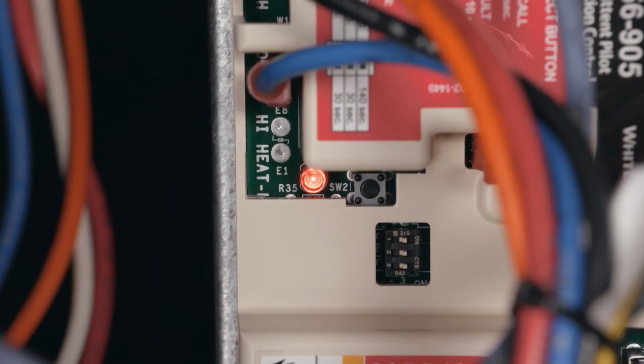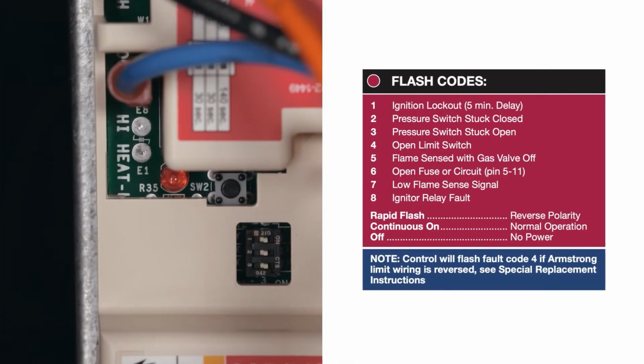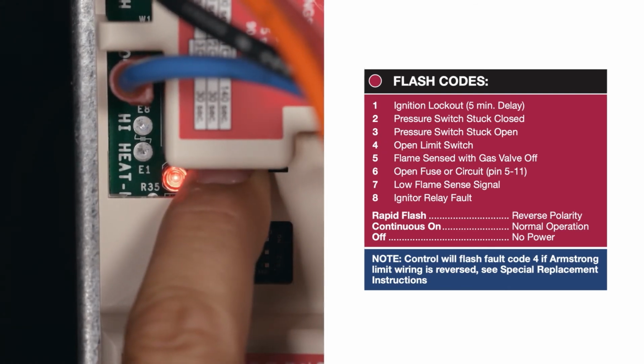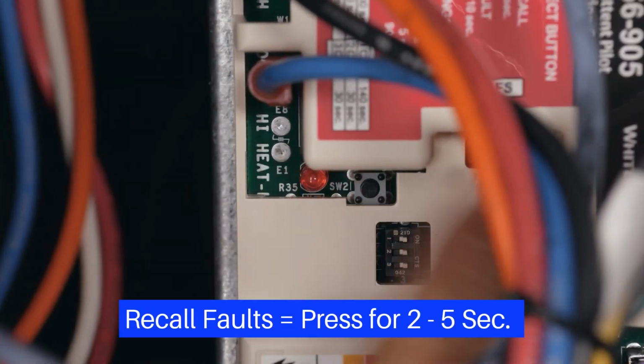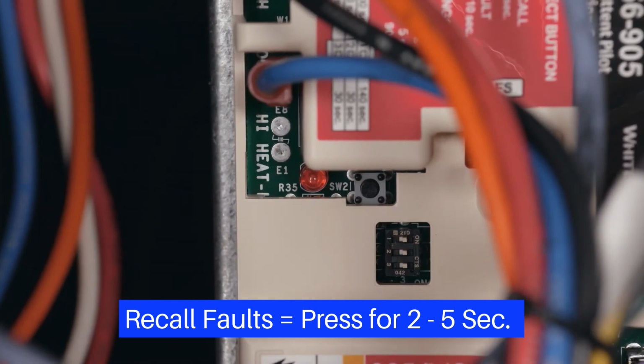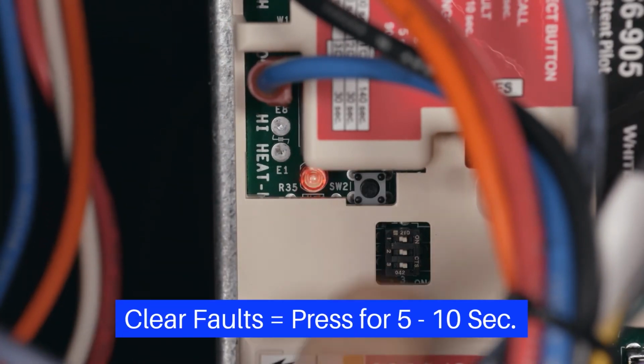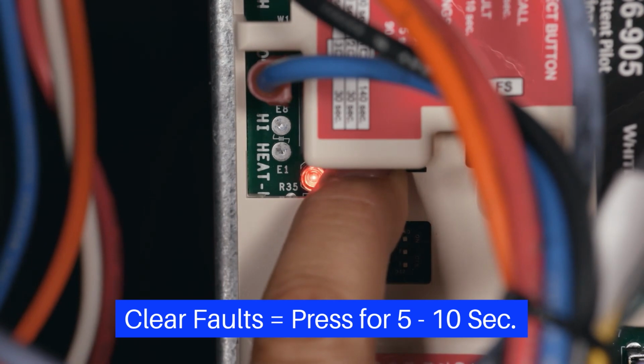The red LED conveys system fault codes. If any faults occur during the cycle, a flash code will indicate the fault. The LED is displaying 4 red flashes. The fault code label indicates a limit or flame rollout switch is open. Up to 5 fault codes are stored in the control. To recall previously occurred faults, press the Select button for 2 to 5 seconds, or until the diagnostic LED turns off. To clear the fault codes, press the Select button for 5 to 10 seconds until the LED begins to flash rapidly while in the standby mode.